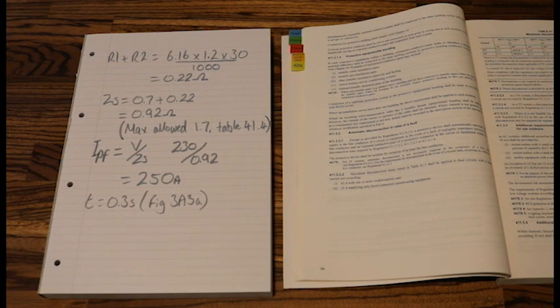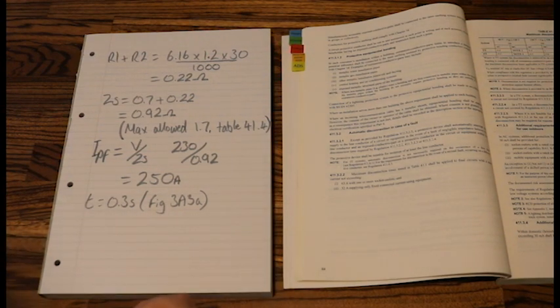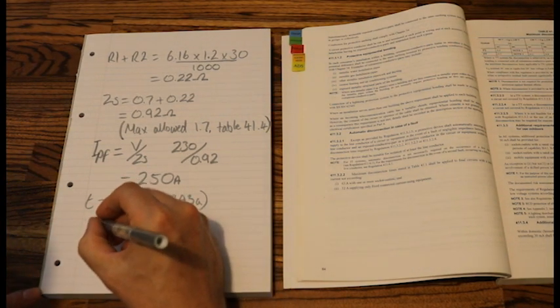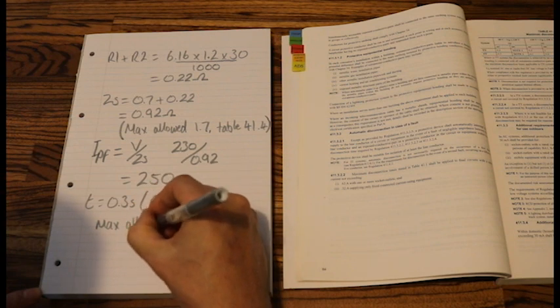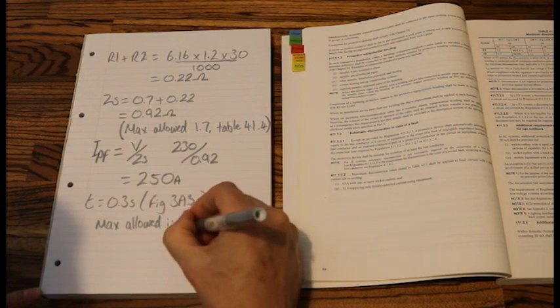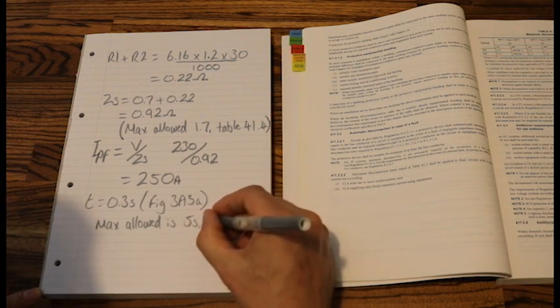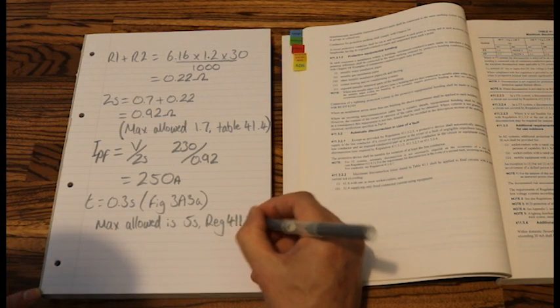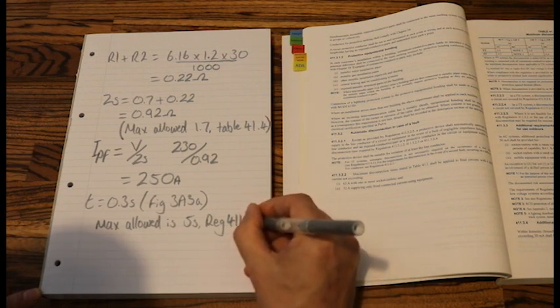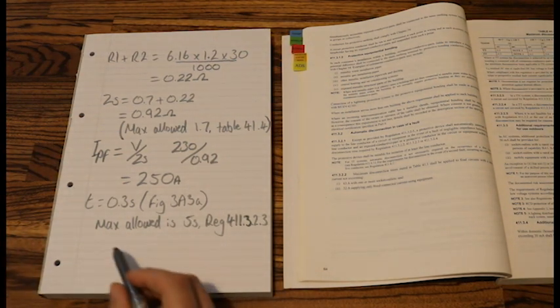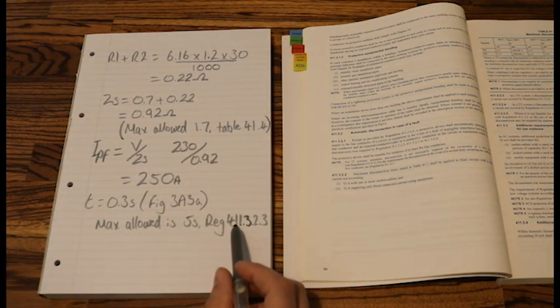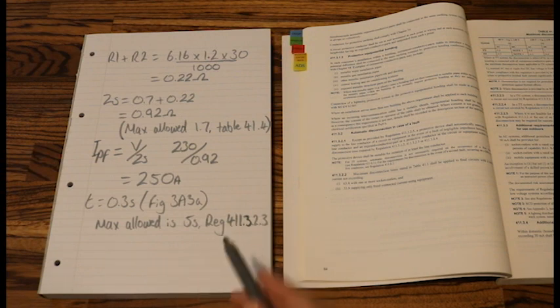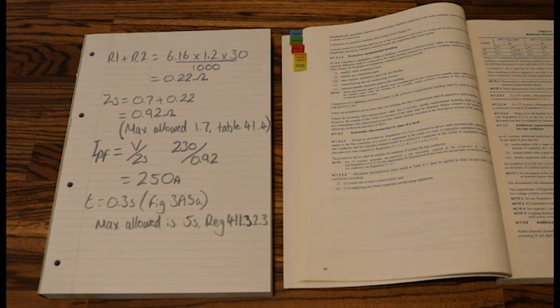So I can go ahead and let's write that down to gain those valuable extra marks. So we have my value of T we've worked out from our log-log graph of 0.3. Now we can write max allowed is 5 seconds and that was from regulation. Always write your regulation numbers that you use to gain those additional marks in your cable calculation question. Max allowed is 5 seconds, regulation 411.3.2.3. And there is how you work out whether your log-log graph, your T value, is compliant with BS7671.